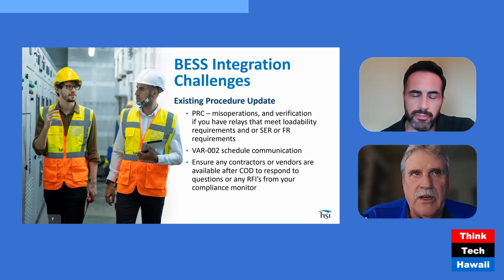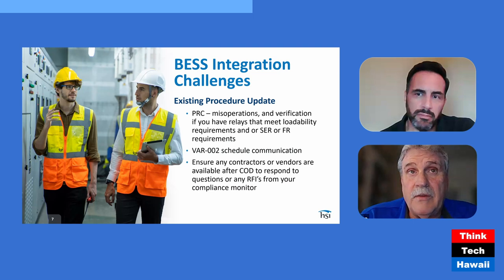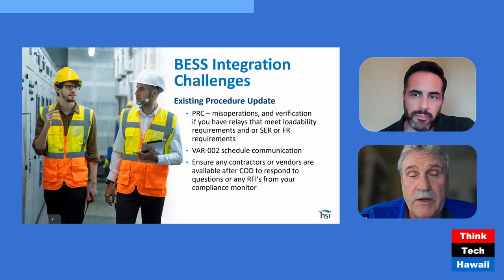If you have an existing facility with a protection system maintenance and testing program in place, you have to perform those operations and testing every so many years, depending on the capabilities of your system. But the clock starts ticking on that time window upon your commissioning date. So if you have an existing facility you've had for two years, and you're going to add battery storage, that facility is going to have protections as well with relays, and that commissioning date is going to start a different clock.